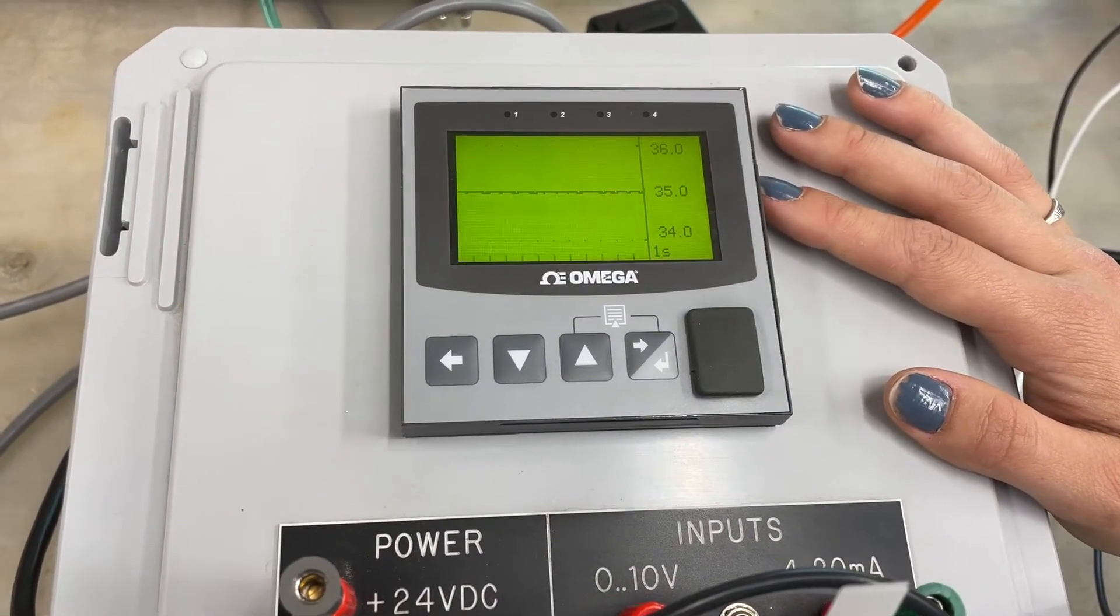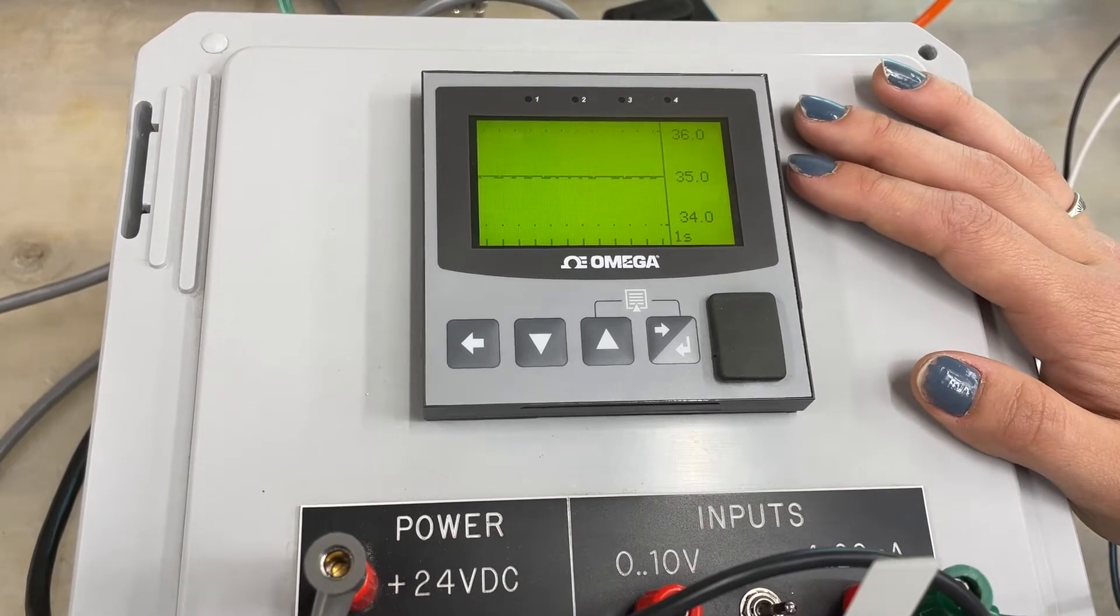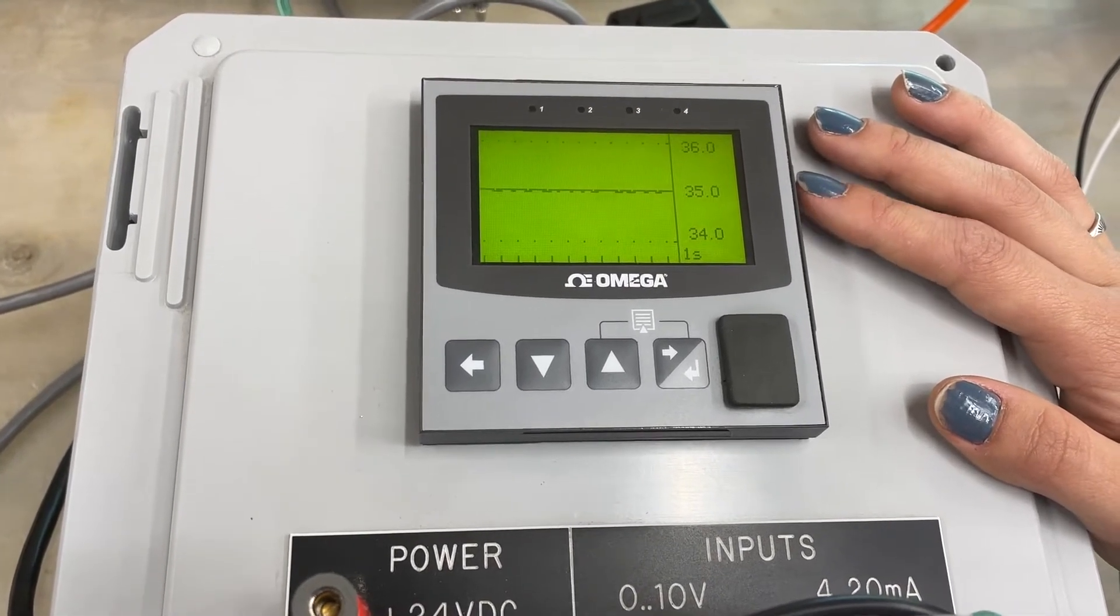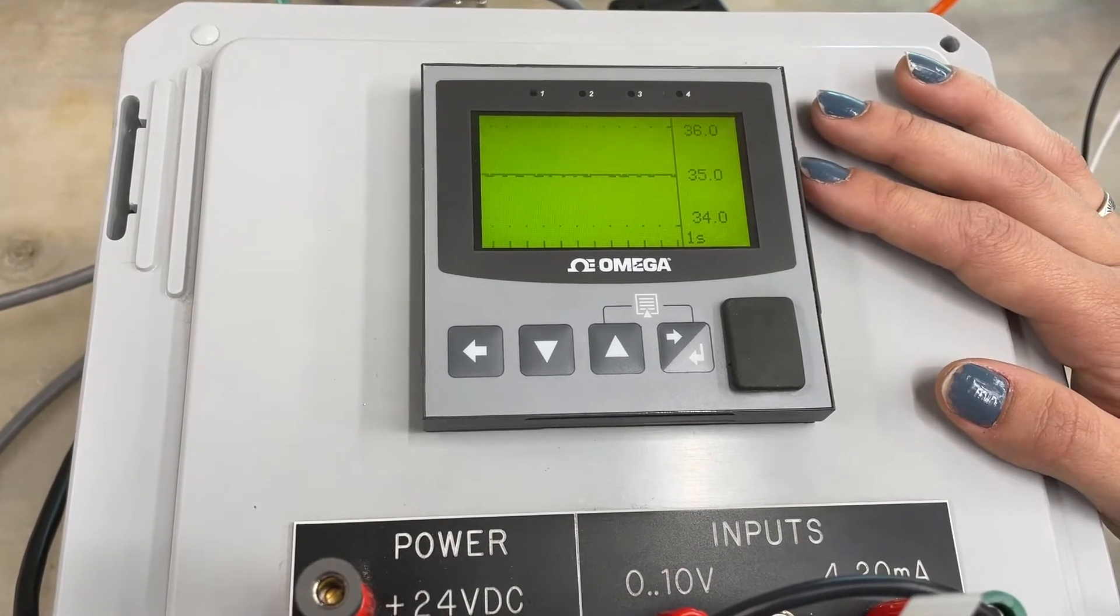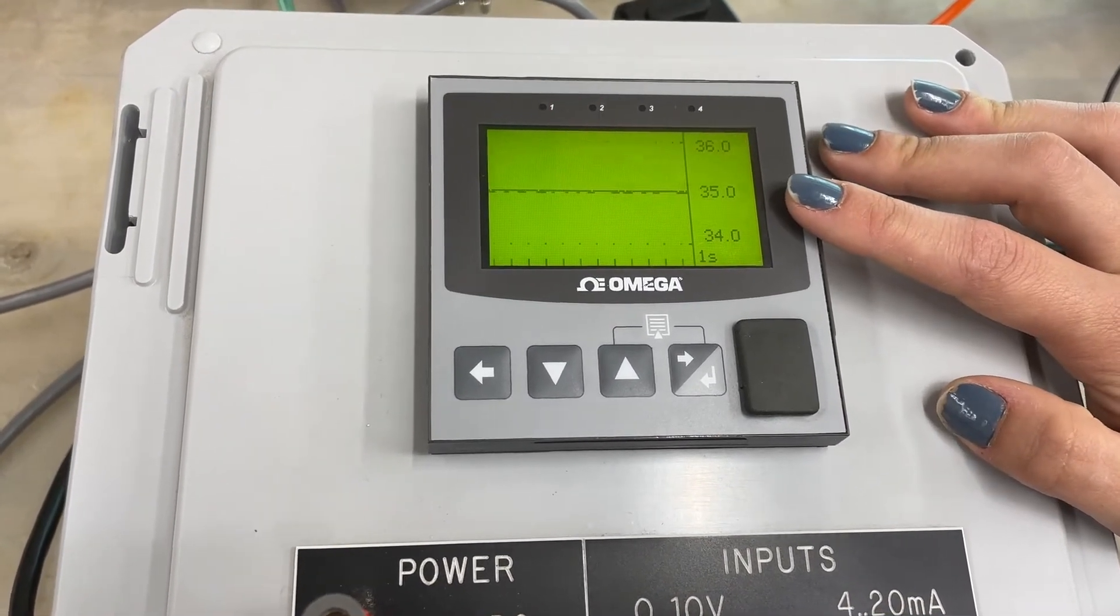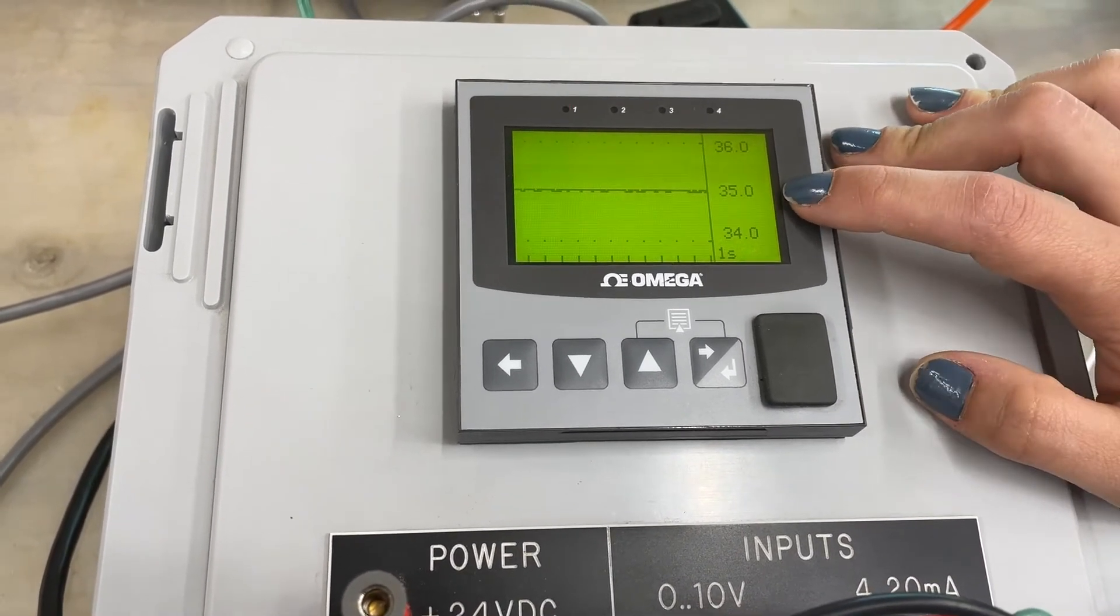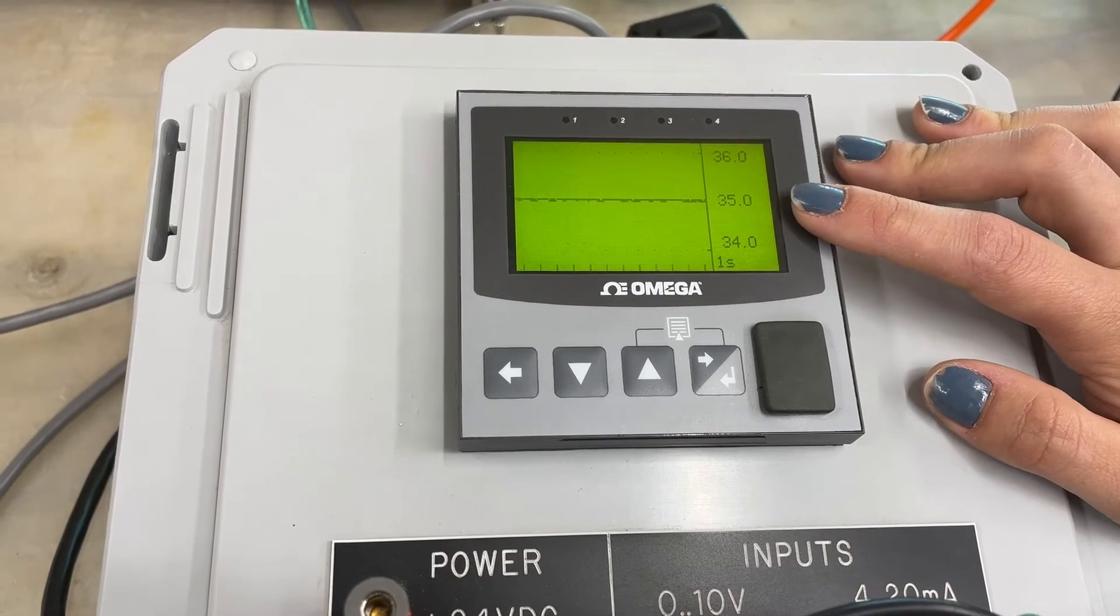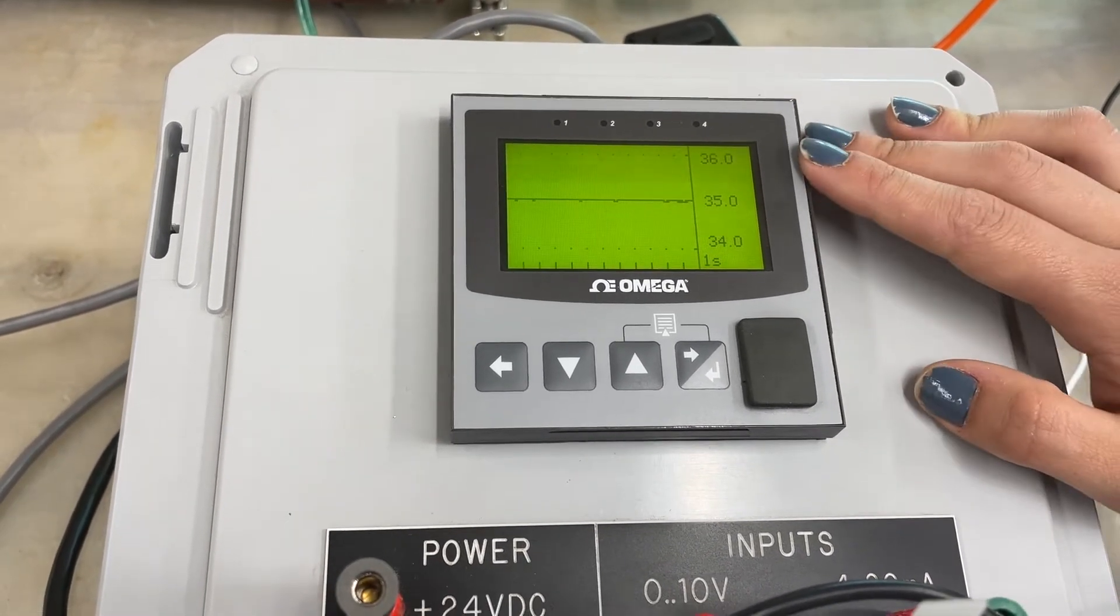Here's the display of the Omega PLC we're using. It is graphing both the flow and the set point. The scale is from 0 to 100% which correlates to 0 to 1000 grams per minute of water through the system. This number in the middle is the measured flow coming directly from the flow meter and you can see right now it's really steady around the set point of 35%. The graph auto-scales so right now it's showing from 34 to 36%.